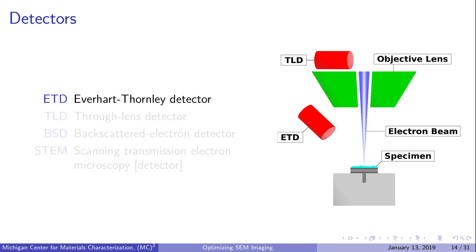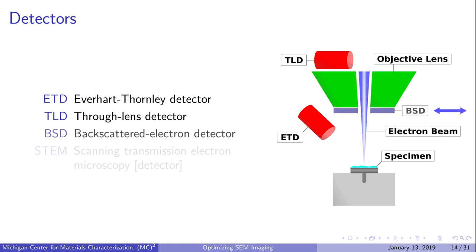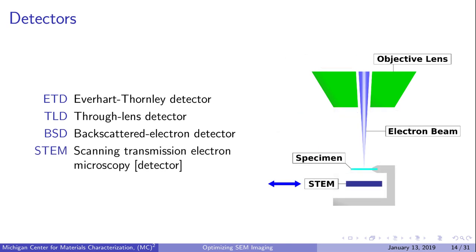The next imaging parameter is the detector used to collect the signal. Let's go over the acronyms and positions of four typical SEM detectors. The Everhart-Thornley detector (ETD) is positioned off to the side at an angle. The through-lens detector (TLD) is typically located above the objective lens and may also be referred to as the in-lens detector. The backscattered electron detector (BSD) is normally retracted and comes in from the side just below the objective lens, shaped like a ring so the electron beam can pass through the middle. The STEM detector is also retractable, disc-shaped, requires a different specimen holder, and sits underneath the specimen.